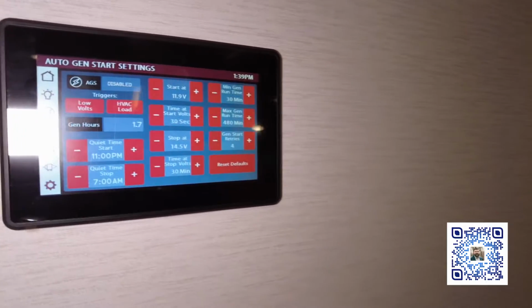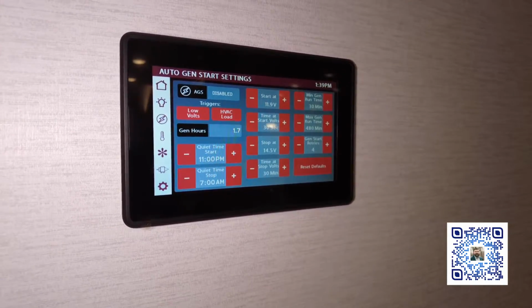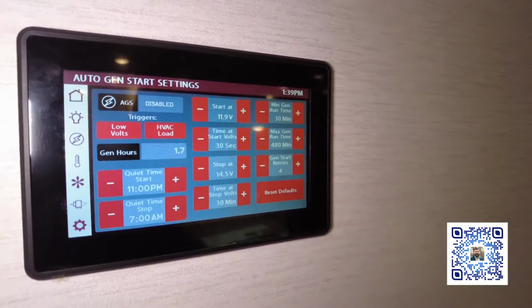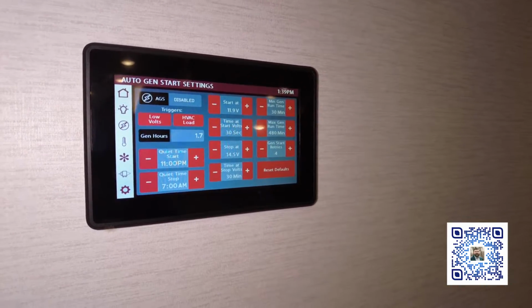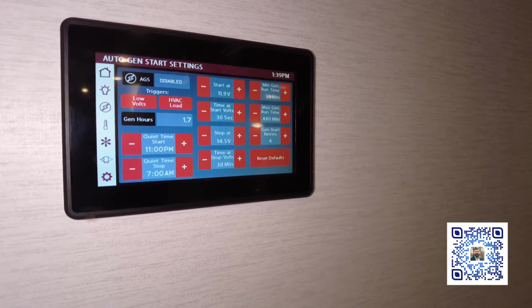So once it gets to 14.5, it'll run for 30 minutes longer. Minimum run time is 30 minutes. You rarely want to start a generator and just shut it right back down. If you're going to start one, let it run for a little bit.